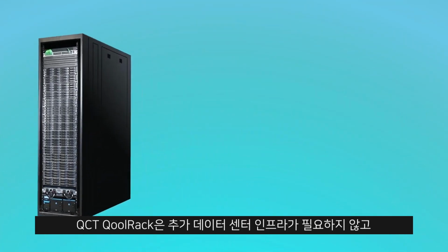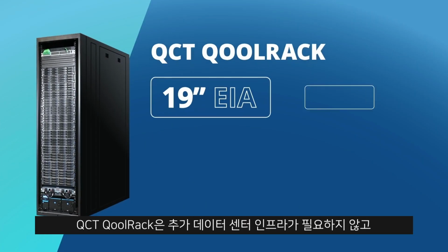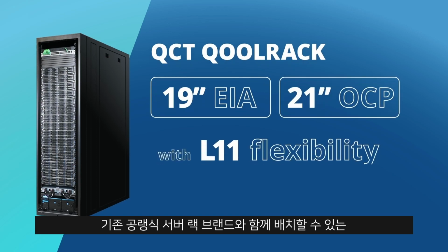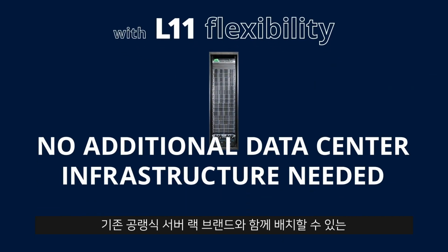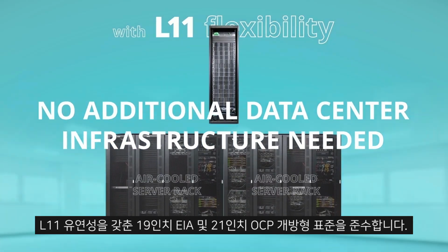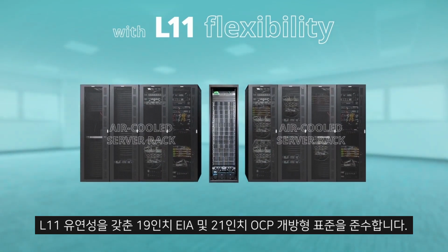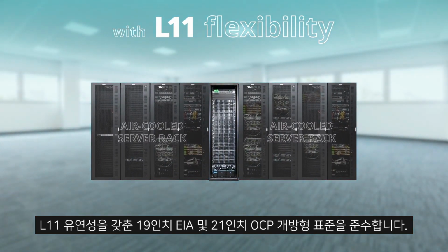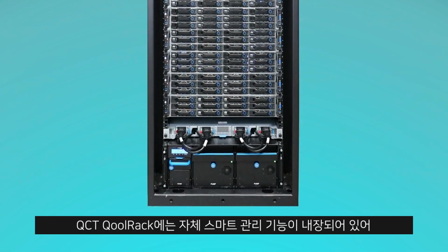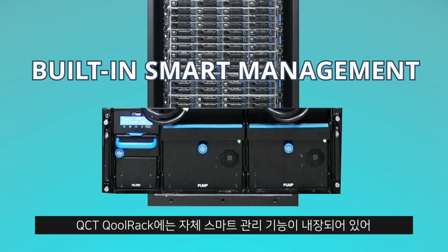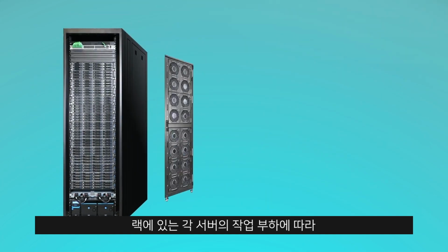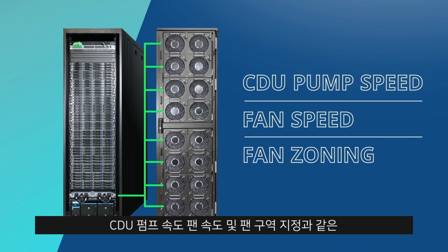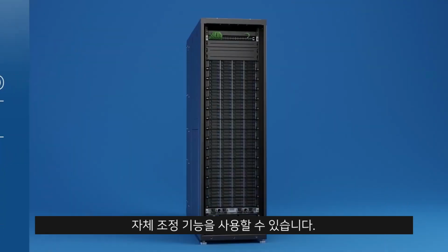QCT QoolRack is compliant with 19-inch EIA and 21 OCP open standards with L11 flexibility, so no additional data center infrastructure is needed, and it can be placed alongside any brand of traditionally air-cooled server rack. QCT QoolRack features its own built-in smart management, which enables self-adjustment functions such as CDU pump speed and fan zoning based on the workload of each server in the rack.